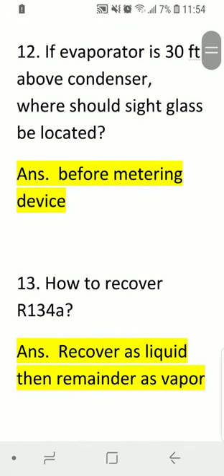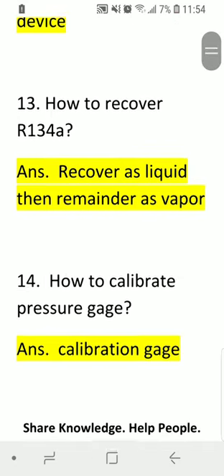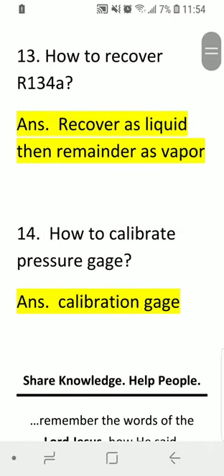Question twelve: if the evaporator is 30 feet above the condenser, where should the sight glass be located? Answer: before the metering device. Question thirteen: how do you recover R134a? Answer: recover as liquid first, then recover the remainder as vapor.